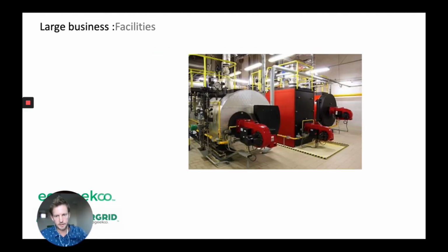The other one is my bugbear with a lot of the way buildings are designed. You'll often have a very big boiler. There's often two boilers, one running lead and one running lag, tied together. They'll be providing hot water, which is then used to run your, say, fan coil units to heat or temper the air that comes into the building. And then the other circuit will be to run your hot water cylinders or your calorifiers throughout the building. If no one was in the building, it doesn't make sense to keep these systems going. It doesn't make sense, certainly for the domestic hot water side.